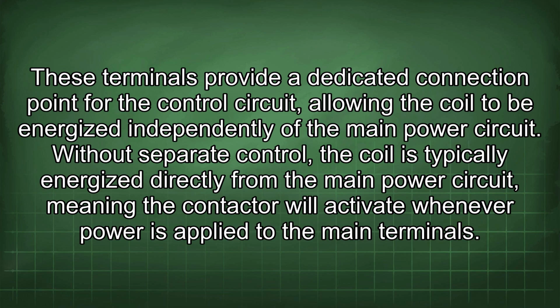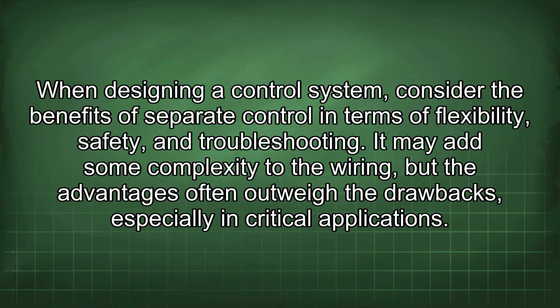Without separate control, the coil is typically energized directly from the main power circuit, meaning the contactor will activate whenever power is applied to the main terminals. When designing a control system, consider the benefits of separate control in terms of flexibility, safety, and troubleshooting. It may add some complexity to the wiring, but the advantages often outweigh the drawbacks, especially in critical applications.